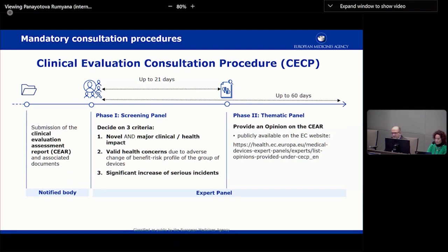The CECP procedure focuses on the notified body's clinical evaluation assessment report — the notified body assesses the manufacturer's clinical evaluation report and produces its own assessment report — and it is on that document and its associated materials that the expert panels provide a non-mandatory opinion or advice. These opinions are publicly available on the Commission's website, though some are redacted while the conformity assessment process is still ongoing.